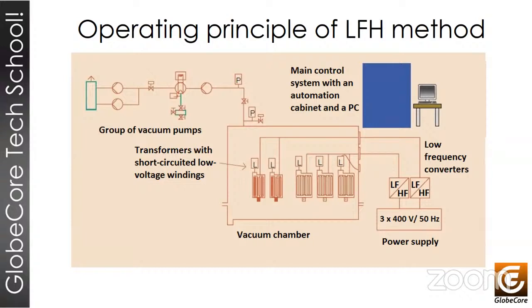Now, let's get to the meat of the bones of the operating principle of the LFH method. The LFH process allows the high voltage and low voltage windings of the transformer to be evenly heated from inside by supplying low frequency and low voltage current into the high voltage windings, while the low voltage windings are short-circuited. At low frequency and low resistance, there arise no high voltage problems, and magnetic bond creates a well-controlled current in the low voltage winding.